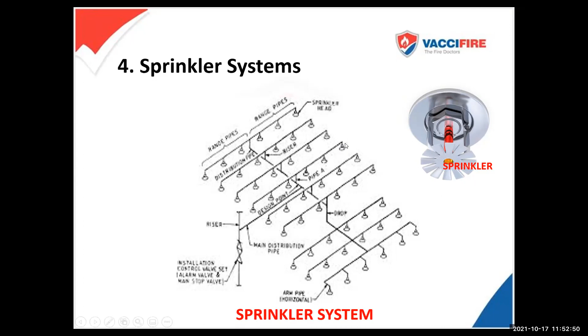This is connected to a separate set of pumps, the sprinkler pumps that he mentioned. This has a pipe network and a sprinkler, which you can see here close up. It has this red color - this is a glass bulb with a filling inside, and this filling expands and bursts the glass bulb at 68 degrees centigrade. So whenever the temperature at the bulb reaches 68 degrees centigrade, the glass bulb will burst, and the water which is in the pipeline behind it will come gushing out and extinguish the fire in the vicinity. That's the sprinkler system.